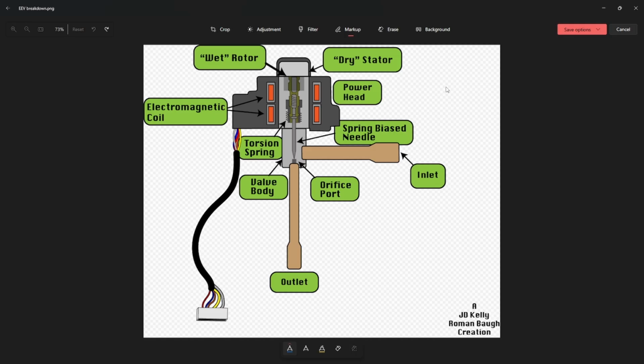It's been that frequent. The majority of the time, you are not going to have an issue with the valve body of an EEV unless you have trash in the system. If there's carbon buildup in the system because somebody didn't braze with nitrogen, and it makes its way in here and stops up this section right here, well, then unfortunately you're going to have to replace the valve body. And I will tell you from my experience with Trane units, it's a pain in the ass process to get a torch in there and try to replace that guy. So hopefully you never have to deal with that.